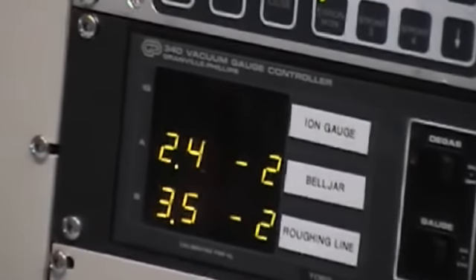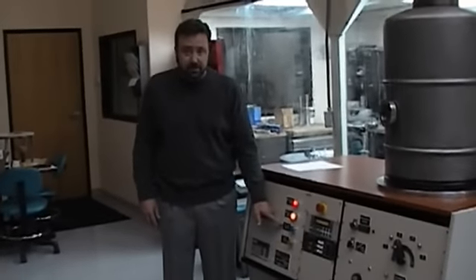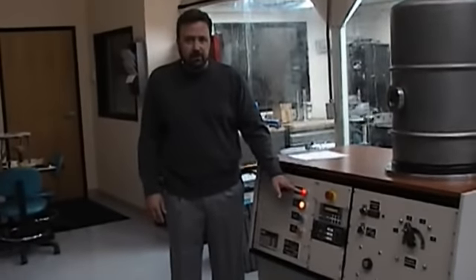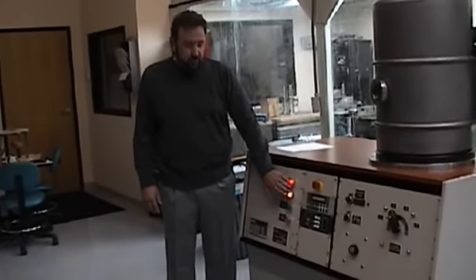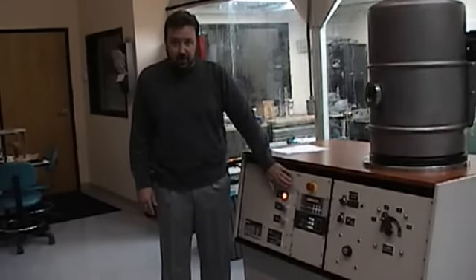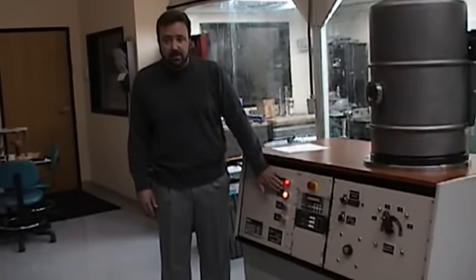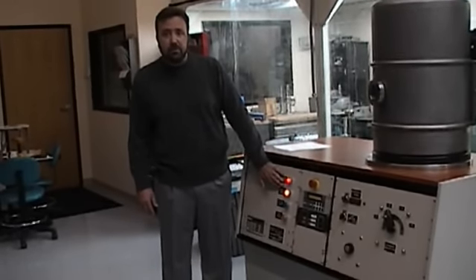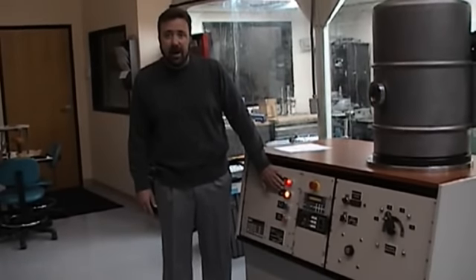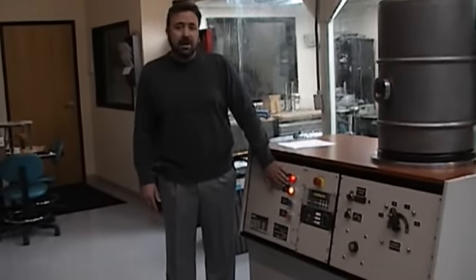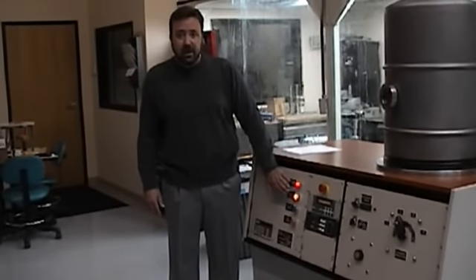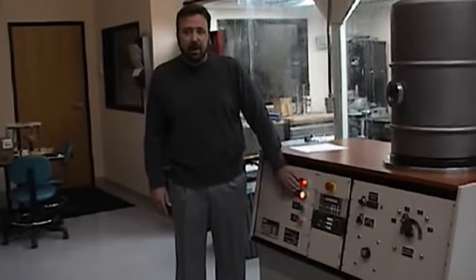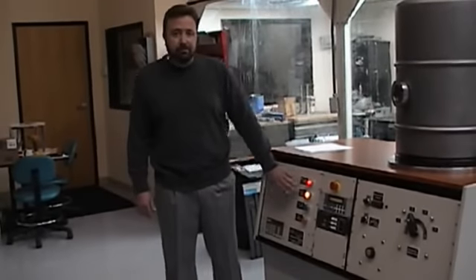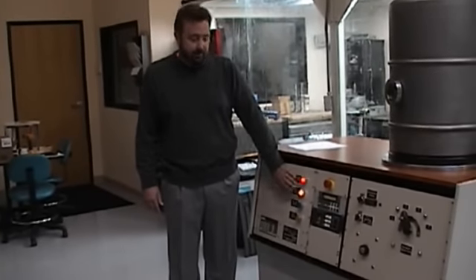What's unique to this system is the cryogenic pump that we're using. I believe previously the class has used a diffusion pump system. Once we achieve our vacuum in the bell jar, we are going to shut off the rough valve and shut off the mechanical pump. Those are no longer needed to stay running. Unlike a diffusion pump, which is a throughput pump and requires a backing pump, the cryo pump is a capture type pump, and it does not require, nor should it have, a pump operating as a backing pump. They operate uniquely different.